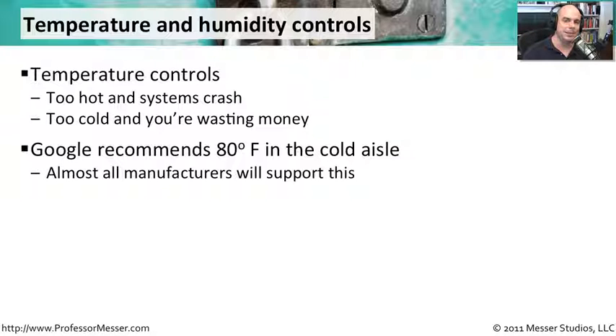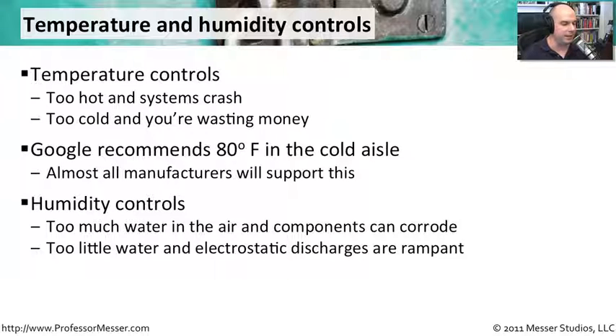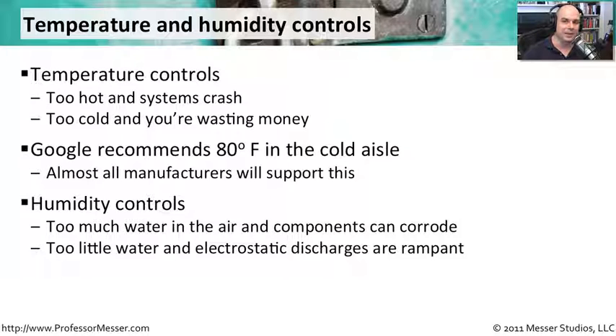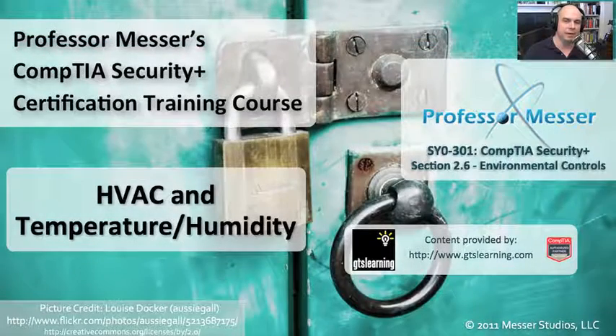It's remarkable how many data centers, though, are keeping things at a lower temperature — that's something you'll have to look at when planning to cool your data center. Humidity is a completely different thing; that's how much water is in the air, and when you're cooling systems, you're removing a lot of the water. So you also have to think about controlling humidity. If you have too much water in the air, you could corrode your components over a very short period of time. If your humidity is too low — too little water in the air — you're going to have a lot of static discharge, and that's something you really don't want around very sensitive electronic components.